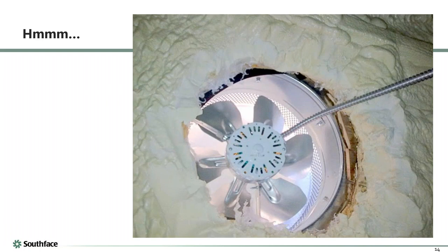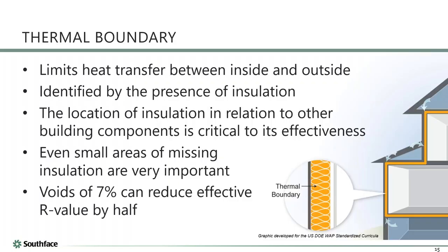Here's a picture illustrating what can go wrong. What's wrong with this picture? It looks like we've penetrated our air barrier just a little bit. Hopefully it's obvious why this is not a good scene — if you foam the roof line, you never want to vent underneath your insulation. At least a couple of people are laughing in the questions, so thank you for that.